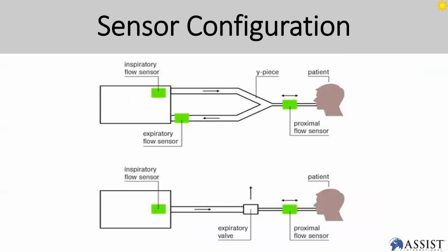So when you talk about configuration of a sensor, normally you're going to see inspiratory flow sensor and expiratory. Some of them you're going to get a proximal flow sensor, depending on the setting of the user and how they're going to work it out. The proximal flow sensor is basically going to capture the reading of inspiratory and expiratory combination together to monitor the total output and input. So these are some additional functions on your ICU ventilator.